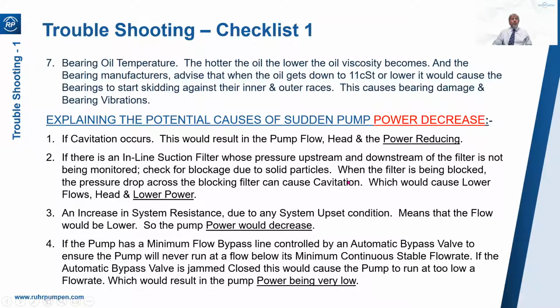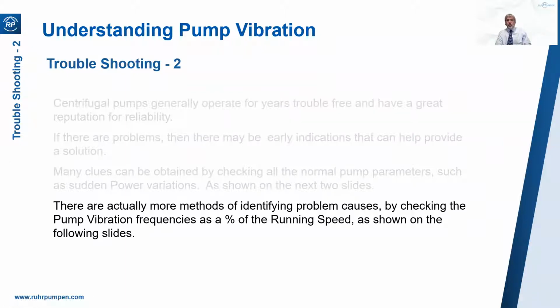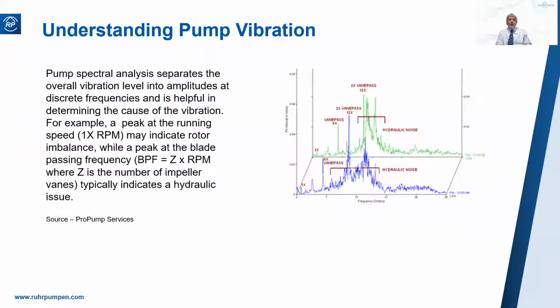Okay, so those are the obvious. Those are the quick and easy things to check when you have a vibration problem. And once you've eliminated the obvious, we can look at vibrations in more detail. Detailed spectral analysis is very much a specialist field. I'm not qualified to lecture on this, and it's certainly well beyond the remit of a 30-minute short course. But this is the kind of analysis that a vibration specialist can offer you. But what I will do in the next 8 slides is vibration analysis for dummies. It's a crib sheet to give you a clue as to what might be happening to your pump at various frequencies.